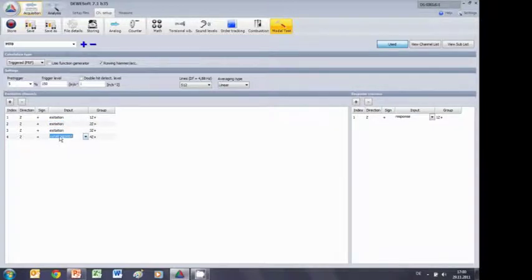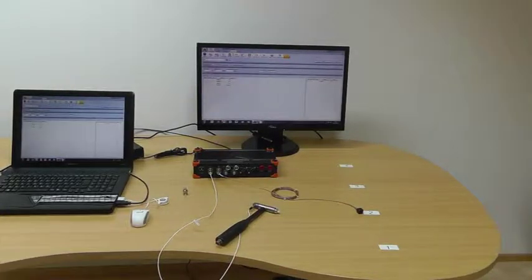These are all my excitation channels, right? And the response channel is already here. Then I also say that I moved my sensor, not on point 1 but onto point 2, so I can say this sensor is point 2. And then maybe give me a couple more lines, maybe 2048 lines. That's it. Okay, this is my whole trigger setup.